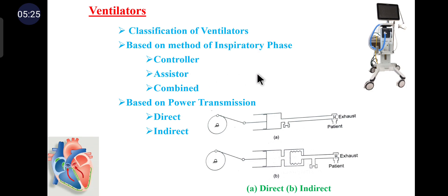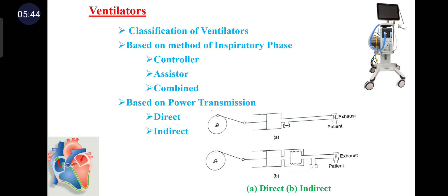In the assistor mode, the ventilator augments the patient's inspiration by operating in response to the patient's inspiratory effort. A pressure sensor detects the slight negative pressure that occurs each time the patient attempts to inhale and triggers the process of inflating the lungs, helping the patient to inspire whenever needed. The combined mode combines both the controller and assistor functions.